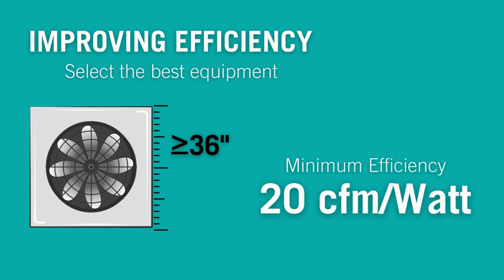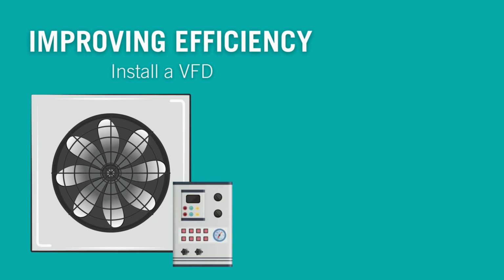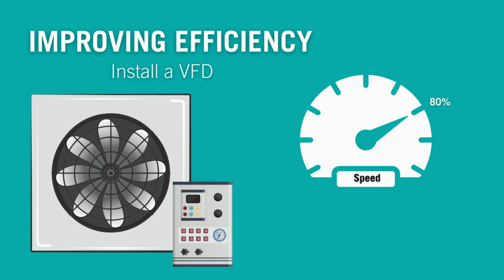Another great way to improve efficiency is to install one large fan instead of several small fans and add a variable speed drive or VSD. Using temperature set points, the fan speed will adjust as needed. Because ventilation fans follow the affinity laws, a fan running at 80% speed will only be using about 55% power.